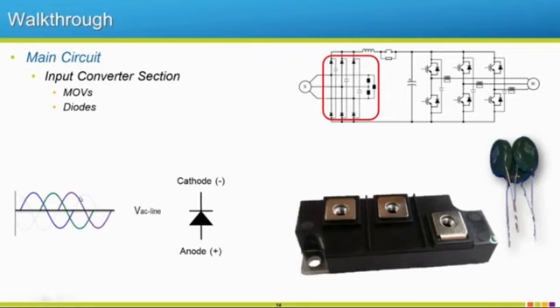So it's going to kind of chop this AC in half and convert it to something that looks like DC, which it will evolve from this as we move to the next section of this drive. So we have our three phase incoming, 120 degree electrically isolated phases coming through here that get chopped in half. So this lower portion would be missing until we come over to our other side of our diode, which this diode right here has the upper and lower portion all in one module.